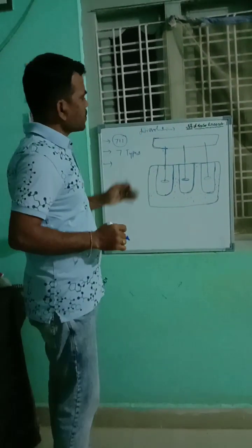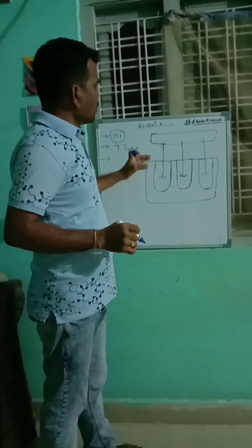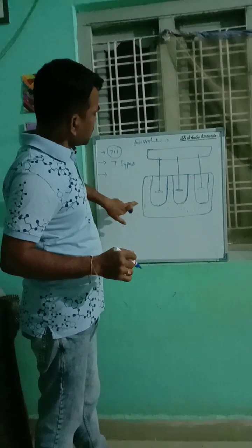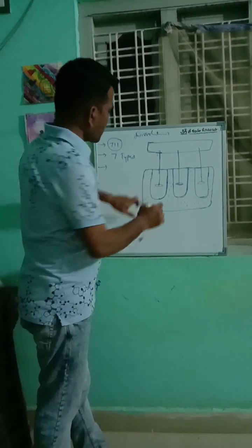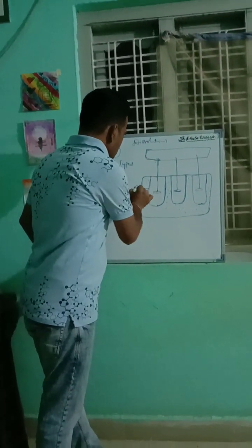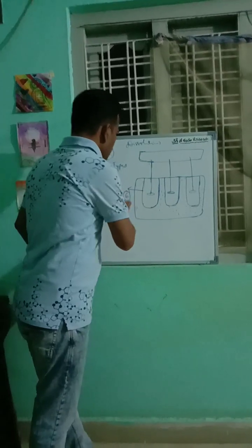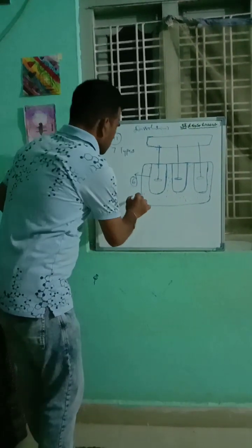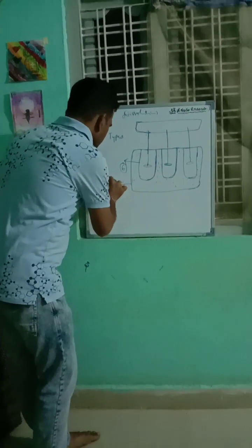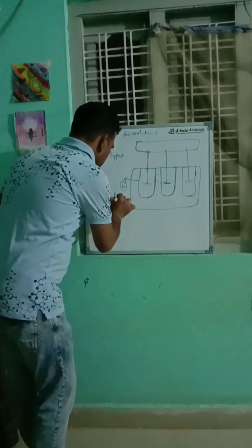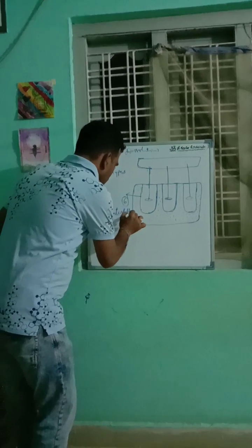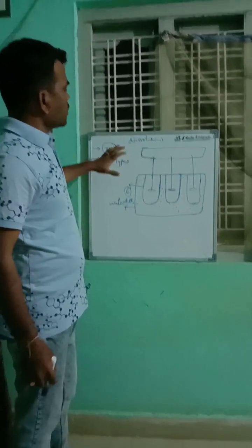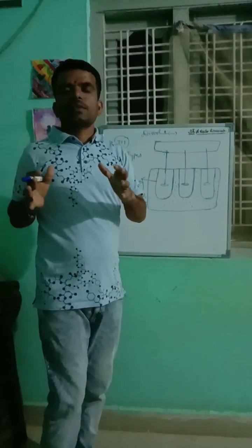In the dissolution instrument, mainly we have to see this water bath, and these are the vessels. 6 vessels are there in each dissolution instrument, and this is the water bath. Here some fixed parameters are there.